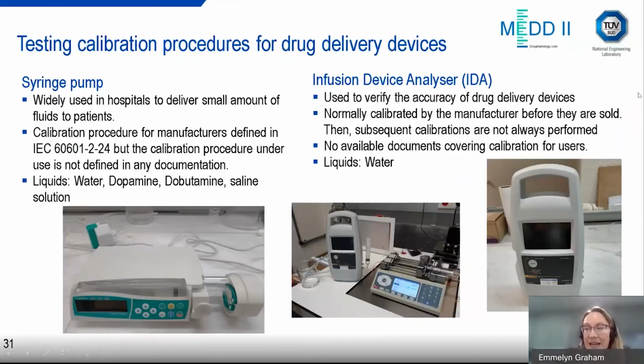If you look at the images at the very bottom, you can see in the center there is a syringe pump which is set up. The liquid, the water, is flowing from the syringe pump through the device analyzer and into a beaker. So the infusion device analyzer is being used to test and calibrate the syringe pump, and that's how it would be used in testing laboratories or hospital labs to verify the other equipment. But you want to make sure that your infusion device analyzer has actually been calibrated and has a low uncertainty before you're using it to calibrate other instruments.